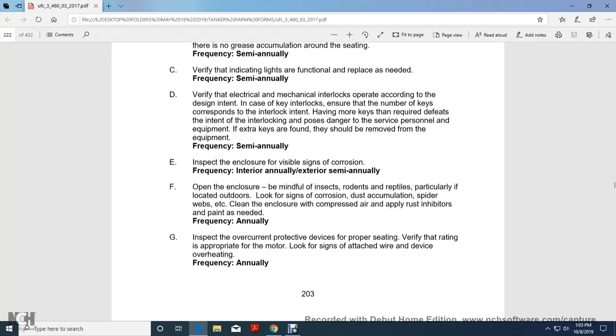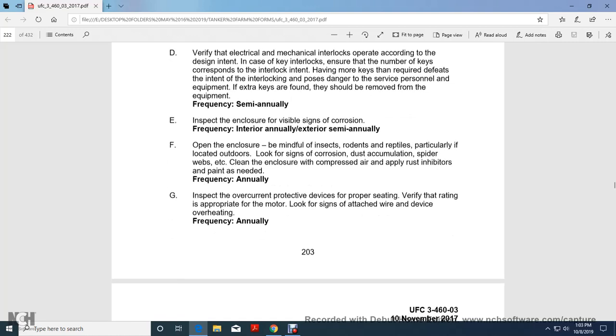Be mindful of rodents and reptiles, particularly where located outdoors. Inspect for signs of corrosion, dust accumulation, spiders, and webs, and clean the enclosure with compressed air. Apply rust inhibitors and paint as needed, annually. Inspect overcurrent protective devices and power components, and verify that the rating is appropriate for the motor.